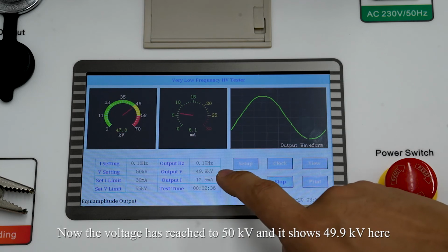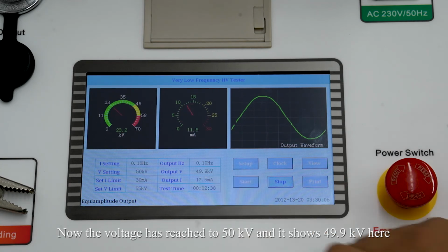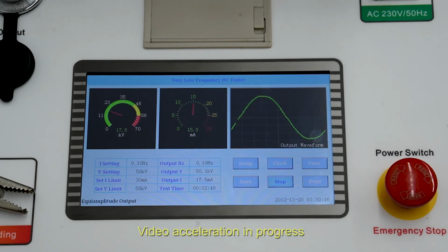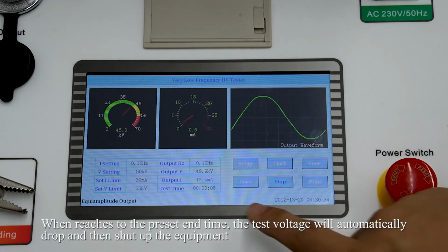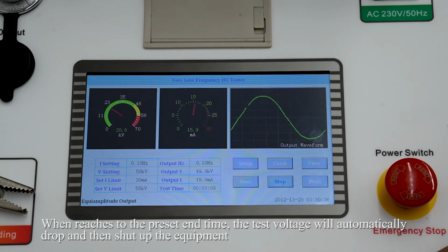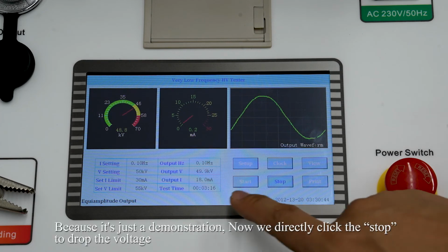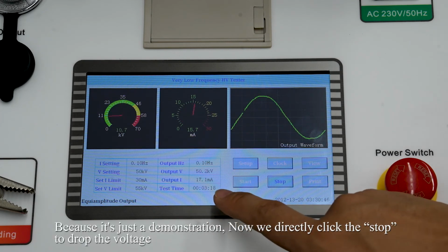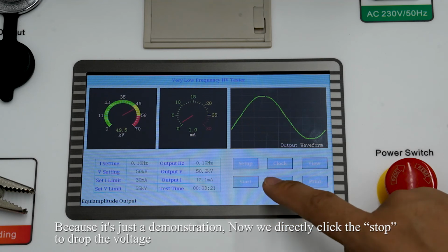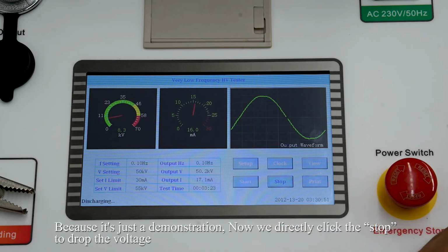Now the voltage has reached 50 kV and it shows 49.9 kV here. When the preset end time is reached, the test voltage will automatically drop and then the equipment stops. Because it's just a demonstration, now we directly click stop to drop the voltage.